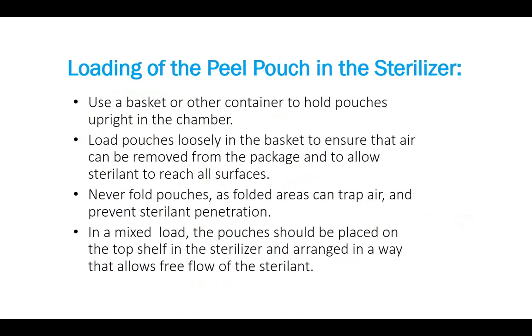Loading of the peel pouch in the sterilizer. Use the basket or other container to hold pouches upright in the chamber. Load pouches loosely in the basket to ensure that air can be removed from the package and to allow the sterilant to reach all surfaces. Never fold pouches, as folded areas can trap air and prevent sterilant penetration. And we know with steam sterilization, you run a Bowie-Dick test to make sure there's no trapped air. So if you're folding that pouch and there is trapped air inside there, the sterilant is not going to get there.